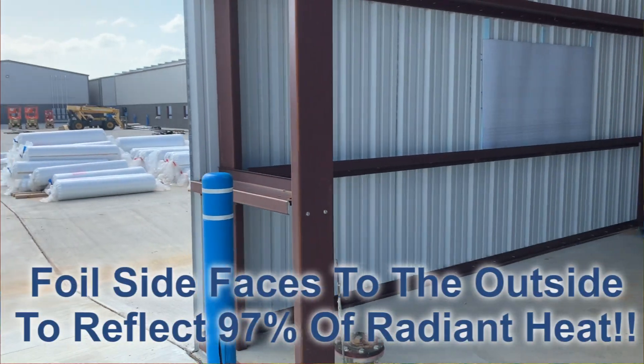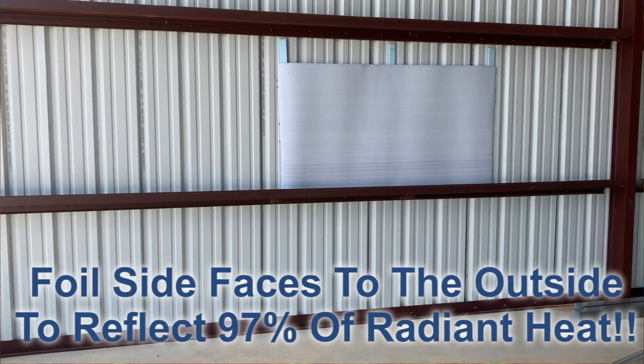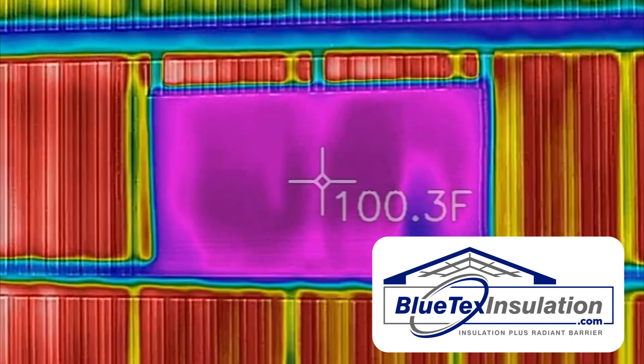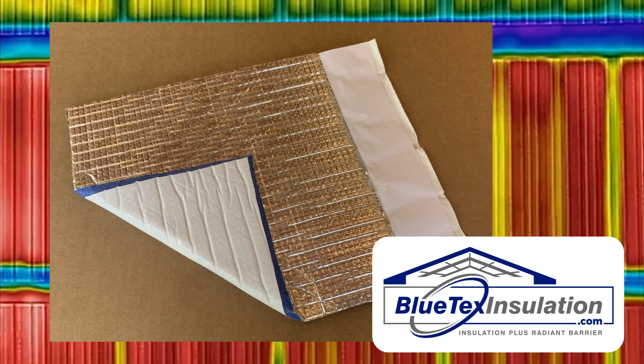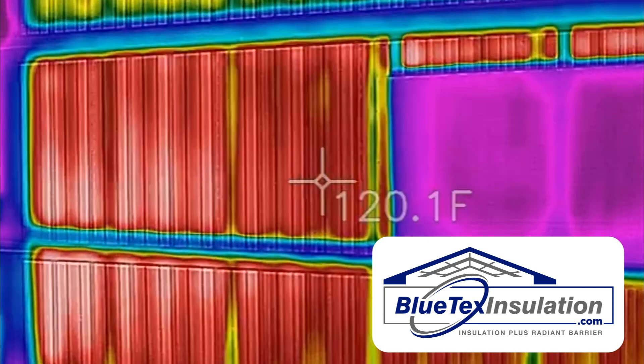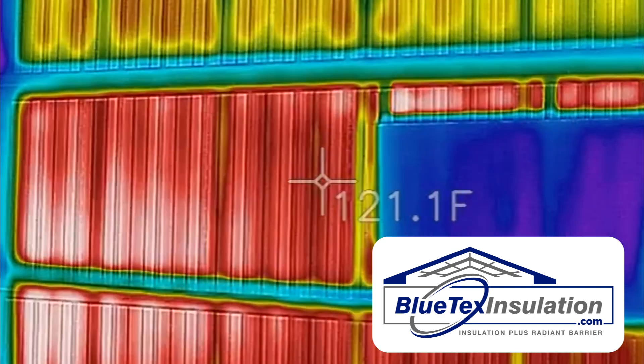If you look, you'll see a piece of BlueTex insulation on the side of the metal building with half-inch foam spacers. Now, on the inside, you can see the inside surface of the 6mm BlueTex foil — foil on one side and white on the other — is about 98, 99 degrees, and the inside of the metal without the BlueTex is about 120, 121 degrees.